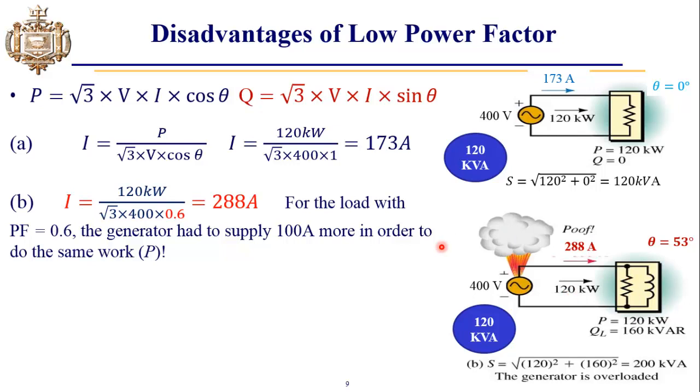So in order to provide this much current, what will be the capacity of the generator? Again we have to compute P and Q. In that case, P comes out to be 120 kilowatts and Q, which is the waste of power, comes out to be 160 kVAR.